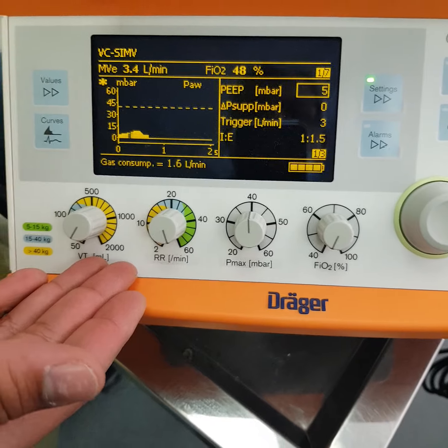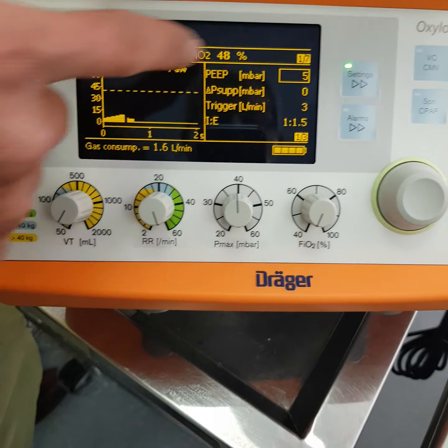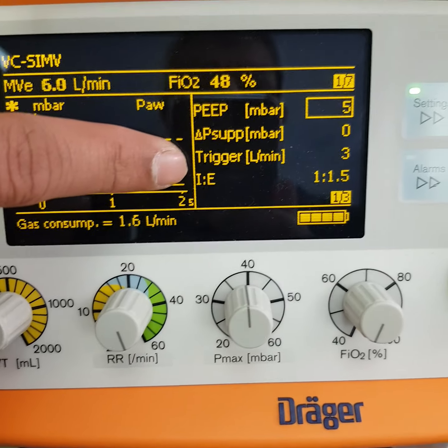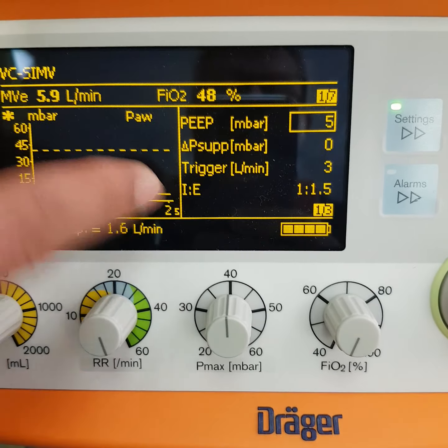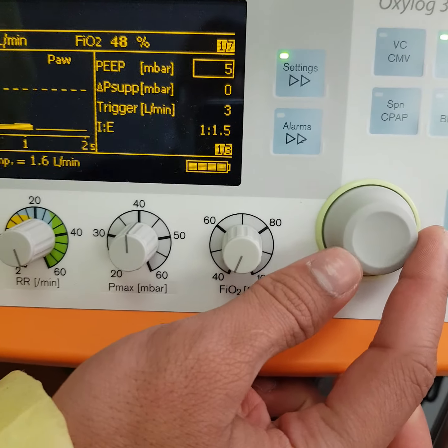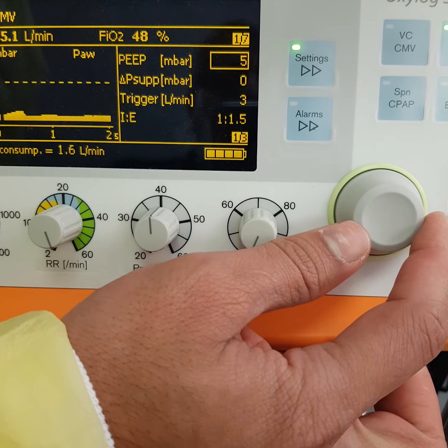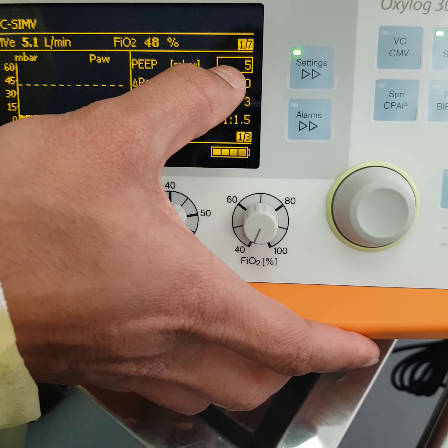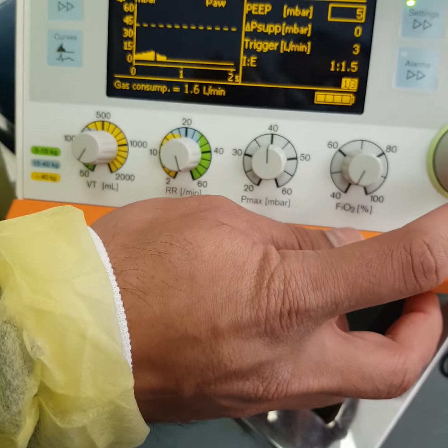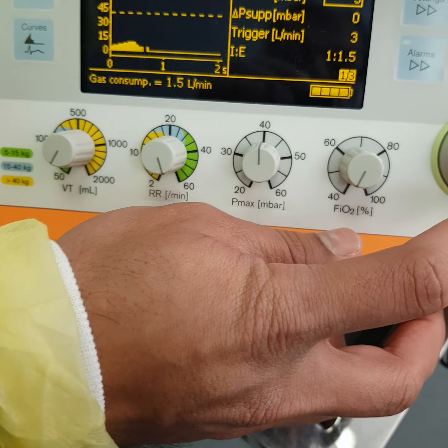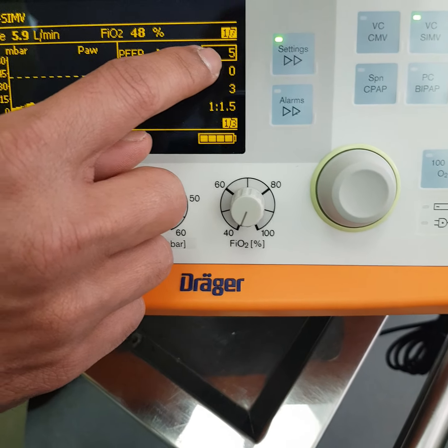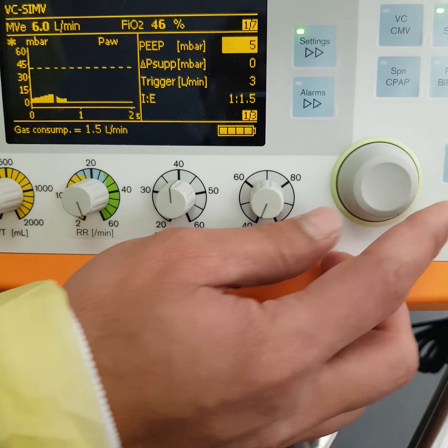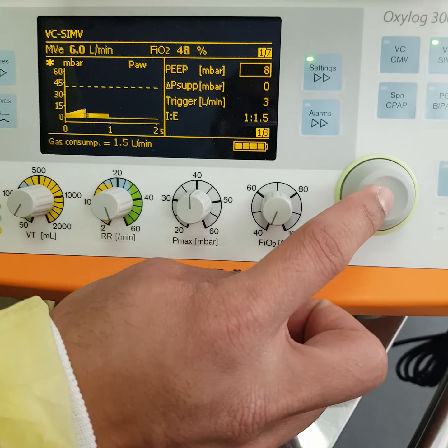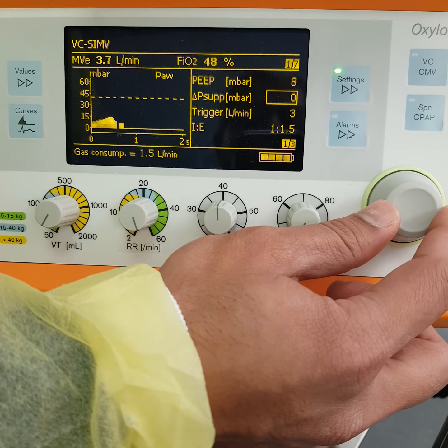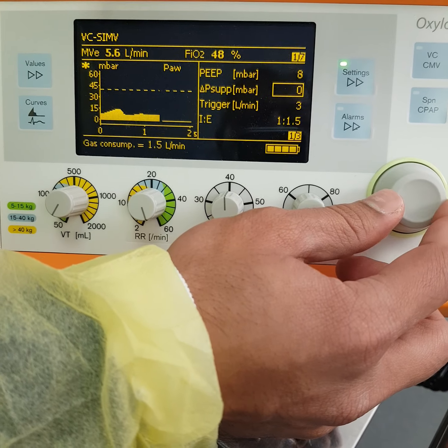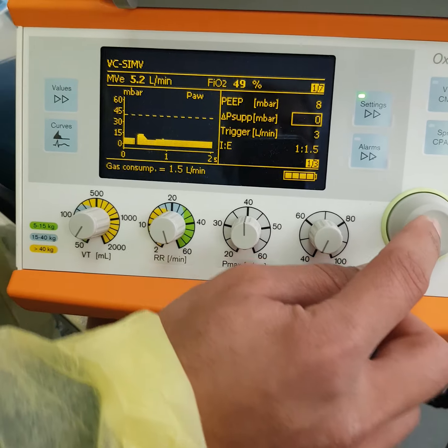So once you are done with these key parameters, you can ventilate a patient, and then you can look at the screen. There are some additional parameters that you can adjust inside the screen with this rotary knob again. You can rotate the rotary knob to select the parameter that you want to adjust. For example, PEEP. PEEP is always kept at a default of 5 centimeters of water. If you want to adjust the PEEP, you use the knob and confirm. You have to rotate and confirm again to select the parameters. The same goes for the other parameters as well. If you want to adjust the pressure support, trigger, I:E ratio, you are going to do the same thing.